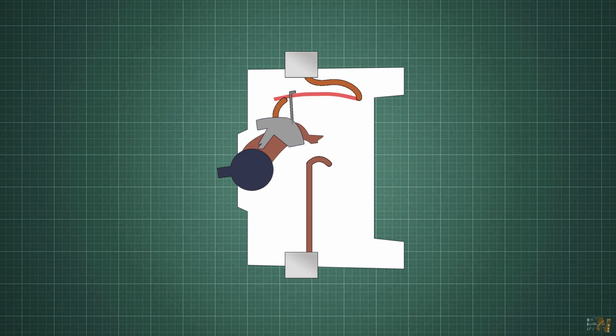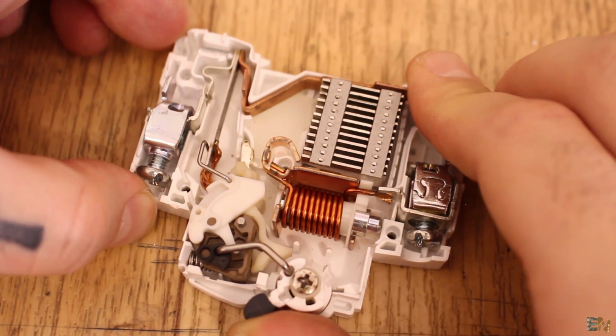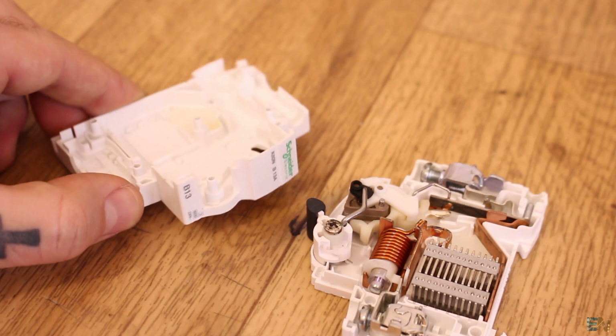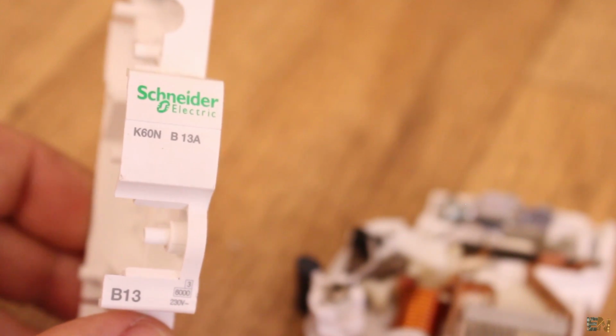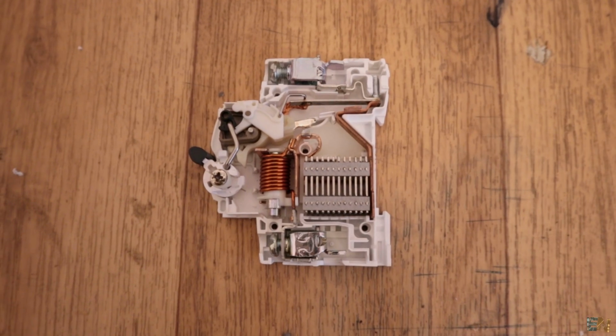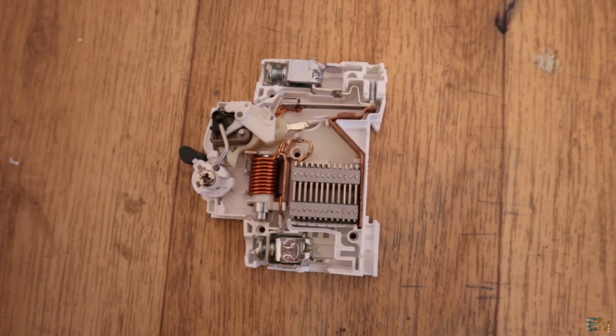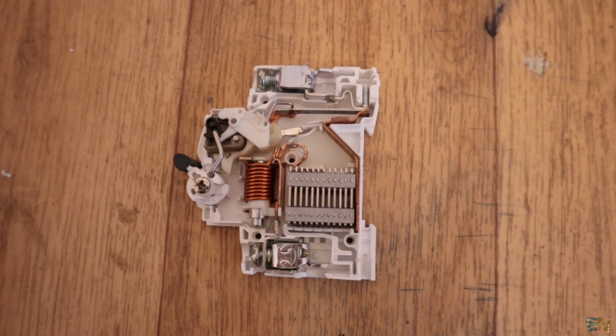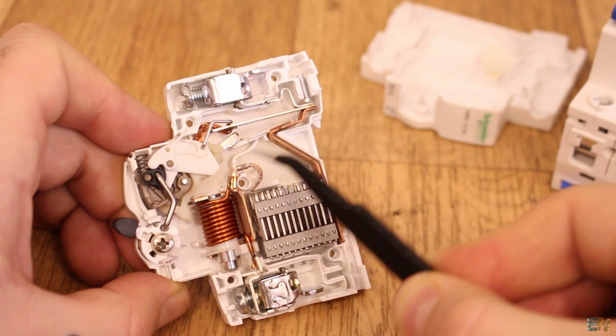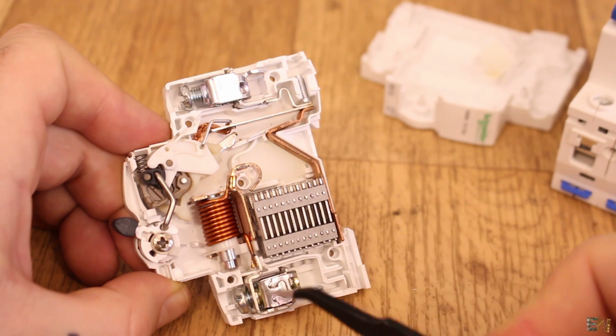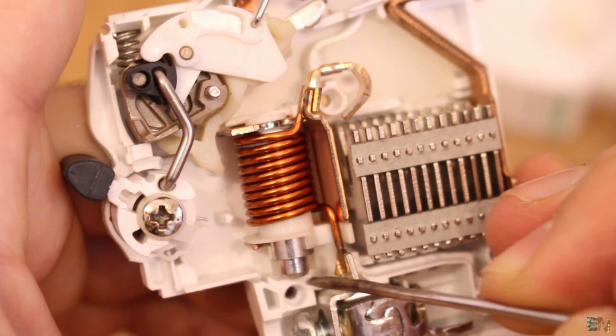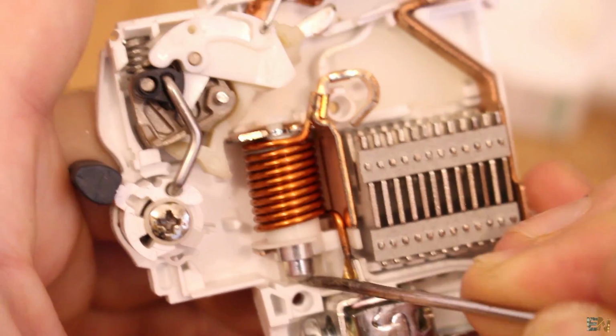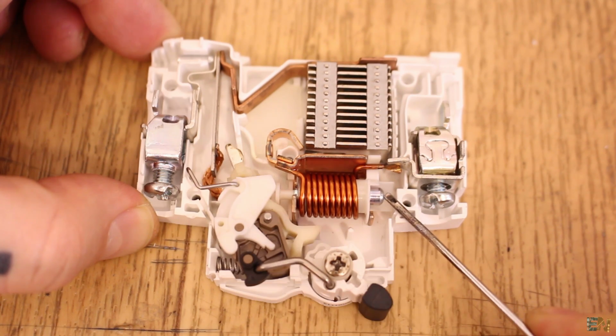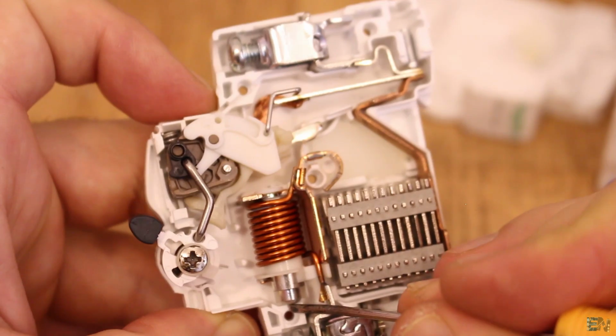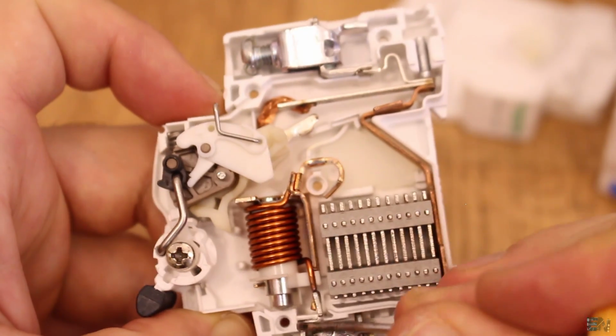But now, how does the magnetic part of this breaker work? Well, first of all, this protection is for short circuits. Since we have a B13, the B will mark that it's rated to 3 to 5 times the 13 amps when a short circuit occurs. And as you all know, when we have a short circuit, a huge amount of current will pass instantly, because the resistance is practically zero. Now the current path is through this coil here. So the huge amount of current will create a strong magnetic field that will push this piston up, instantly. That once again will release the actuator and interrupt the circuit. So that's how the magnetic part of this breaker works, and protects the wires from short circuits.